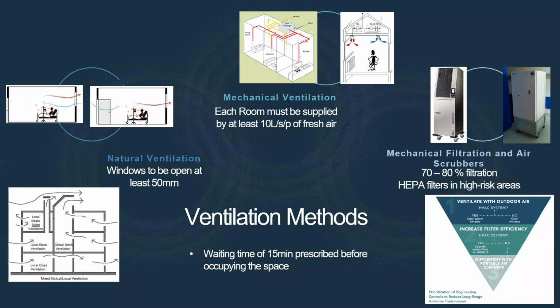So from a legacy point of view, and that's why I briefly touched on the combination of the two systems, in the older, pre-1990s facilities, the ventilation regimes drastically changed from what we have today. And the fresh air component in certain instances is much less than the prescribed requirements that we need to satisfy in older facilities. So by combining the two ventilation systems, you can actually achieve 10 liters a second per patient, and better, by actually having fresh air discharge, pressurizing that area, and also opening a window or cracking the window to actually provide you with either a balanced, neutral environment, or a slightly overpressurized or underpressurized one, depending on the type of design of that particular environment that you're operating at.